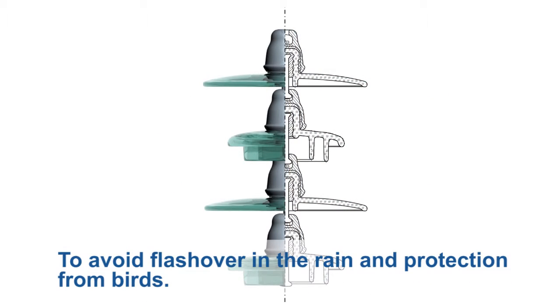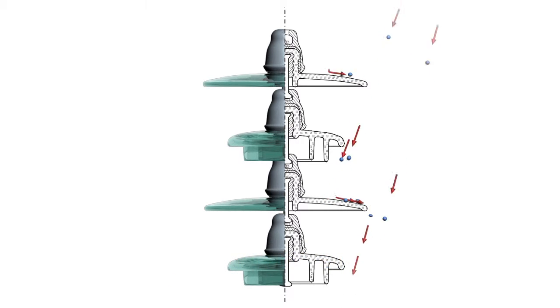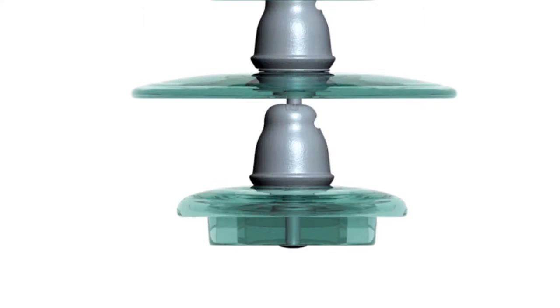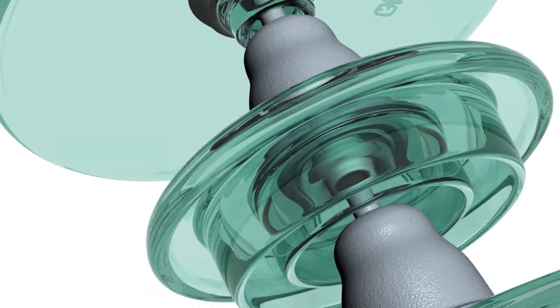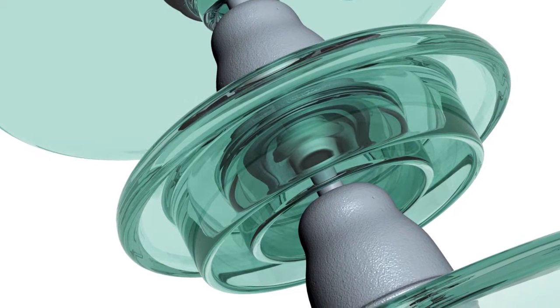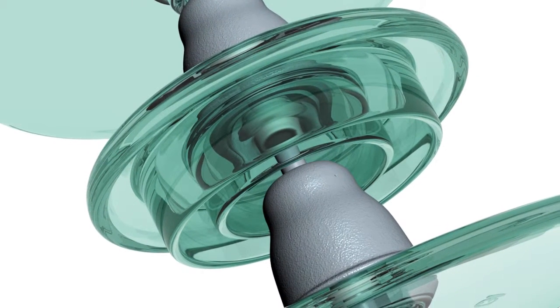The aerodynamic profile shields from water and vertical flowing contaminations, and thus the largest part of the surface of an insulator of the U70BL type and vertical ribs practically create a dry zone in a string unit. This way, configuration of the mixed type string unit prevents generation of a liquid steady flow. The distance between the wetted disc edges is extended. This provides the absence of direct conducting, away from the end fitting along the string unit.